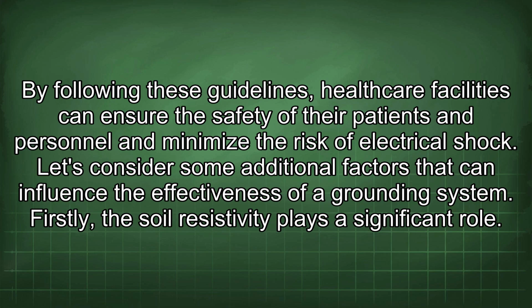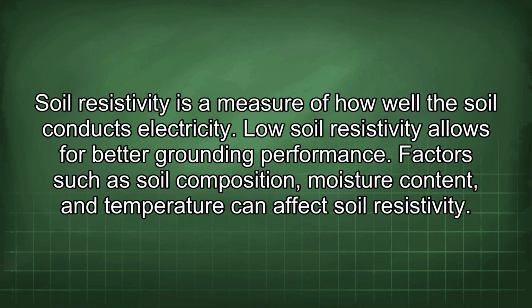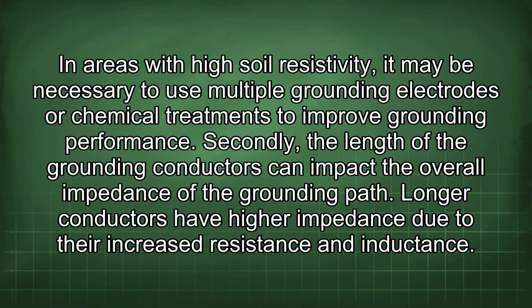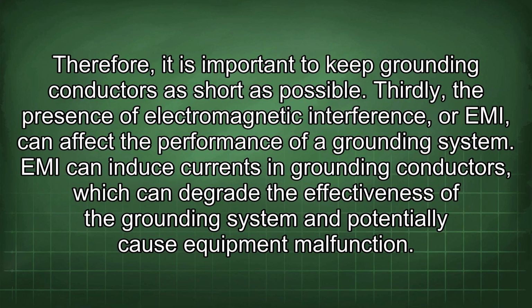electrical shock. Let's consider some additional factors that can influence the effectiveness of a grounding system. Firstly, the soil resistivity plays a significant role. Soil resistivity is a measure of how well the soil conducts electricity. Low soil resistivity allows for better grounding performance. Factors such as soil composition, moisture content, and temperature can affect soil resistivity. In areas with high soil resistivity, it may be necessary to use multiple grounding electrodes or chemical treatments to improve grounding performance. Secondly, the length of the grounding conductors can impact the overall impedance of the grounding path. Longer conductors have higher impedance due to their increased resistance and inductance. Therefore, it is important to keep grounding conductors as short as possible.